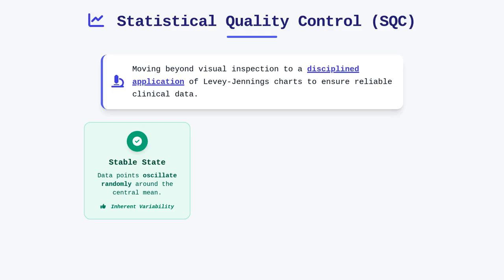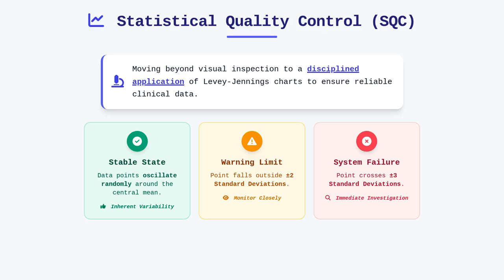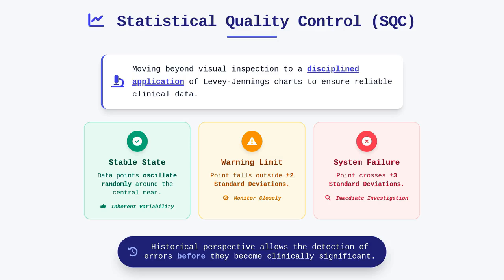Ideally, the data points should oscillate randomly around the central mean, reflecting the inherent variability of any measurement system. If you see a point that falls outside the two standard deviation boundary, you must treat it as a warning, though it does not necessarily demand immediate cessation of testing. However, when a point crosses the three standard deviation limit, you are effectively staring at a failure that requires an immediate investigation into the measurement chain. The power of these charts lies in their ability to provide a historical perspective, allowing you to catch errors before they become clinically significant.